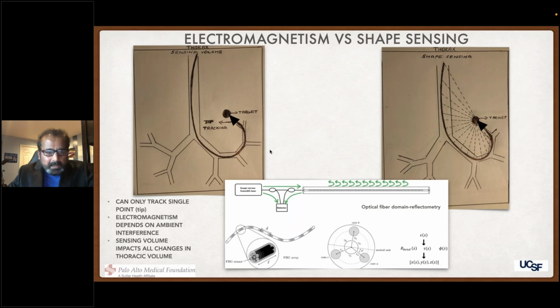So here's the cartoon of the electromagnetism-based system versus the shape sensing technology. In the bottom cartoon, you can see the FBG sensor with the central laser bundle that picks up refraction, and the peripheral 6 bundles pick up the reflection, and they measure twist, bend, rotation, and distortion. And you can see in the top portion with the green arrow, the light that is going through the catheter and reflected back are both picked up by the detector, and that's how the system is able to understand and stabilize the shape of the airway that is leading to the target.